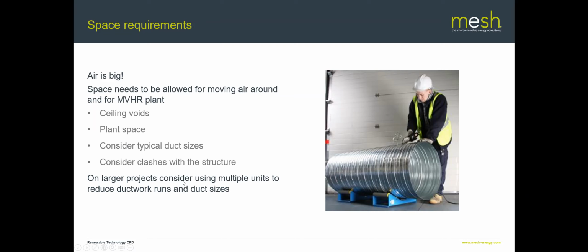So on larger projects, and by larger projects I'm talking about houses of maybe over 300 square meters domestically, it's probably worth considering using multiple units, because that way you can keep the ductwork size down to a reasonable level, and you can have units dotted about rather than trying to run huge ducts from one central location. Just to note, this picture was made to make a point, that's not actually a typical size of ductwork for a domestic installation. That would be a pretty big commercial installation, probably 400 by 800 diameter duct or something. That's not typical.